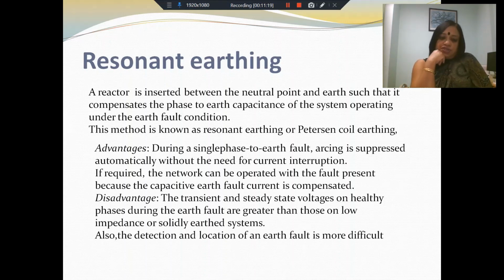There are certain advantages and disadvantages to resonant earthing. During a single phase to earth fault, because of the resonance condition, because the reactance of the inductor balances the reactance of the capacitance, arcing is suppressed automatically, and you do not need any extra current interruption. And that means even if you have a fault, you can still continue to operate the network, because whatever capacitive earth fault current is flowing, that will be compensated by the reactive current that is generated. So if it is necessary to continue to operate the system even under fault conditions for some time, that can be done. But the disadvantage is, of course, the transient overvoltages that can happen.